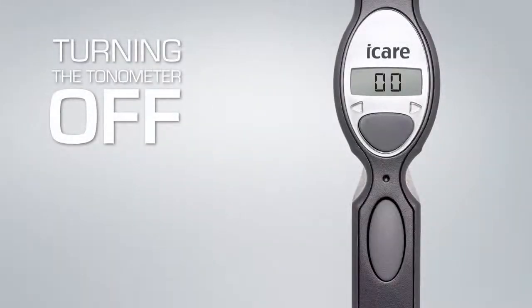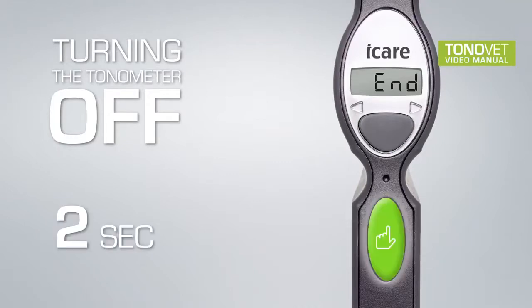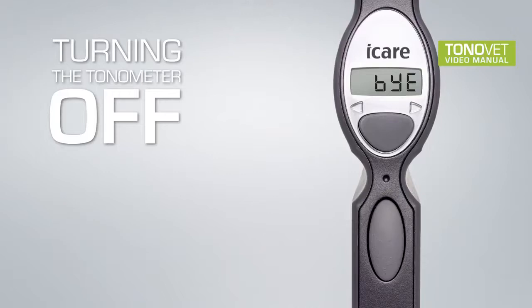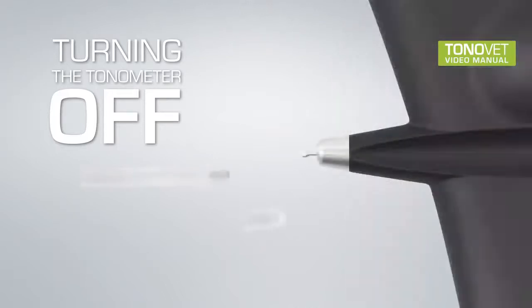Turning the tonometer off. From the starting mode, 0, 0, press the selector button until the display shows end. Press the measurement button for 2 seconds. The display shows bye and the tonometer will switch off. The used probe will be partially ejected.